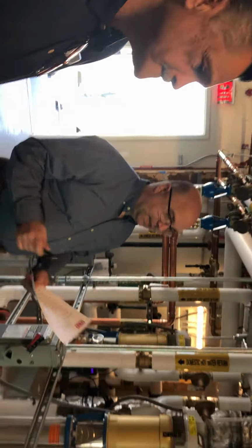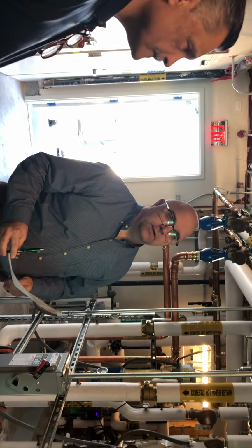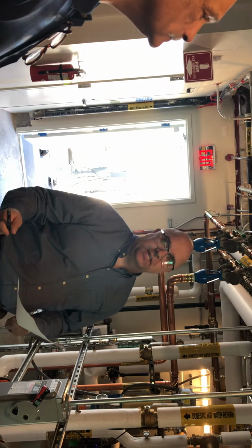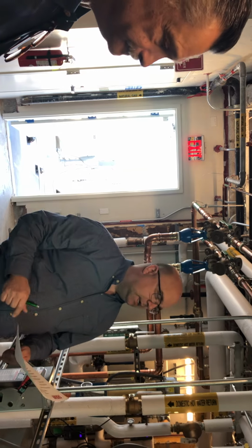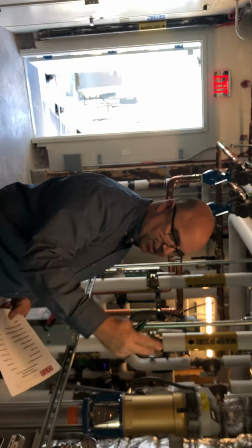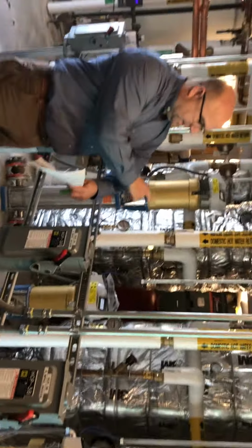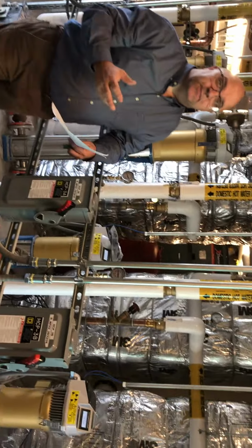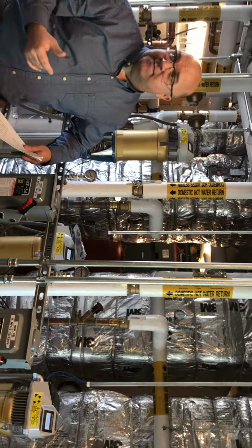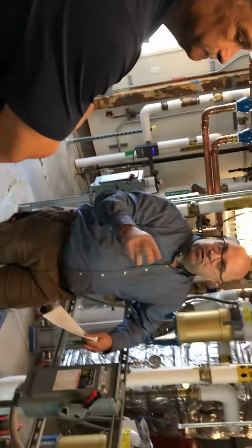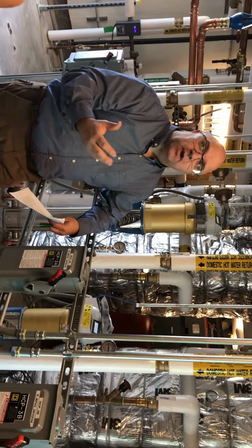Okay, so since we're starting here in the boiler room, the domestic hot water system, which has gotten a lot of attention lately, and we'll show you the boilers, are controlled, the returns are controlled by these hot water pumps. These things basically run themselves, but the control system turns them on and off. Once a week we rotate which one is the one that's running.